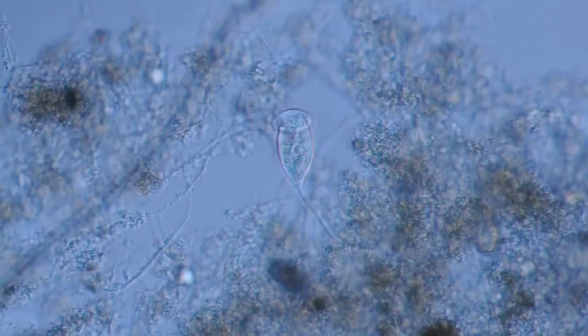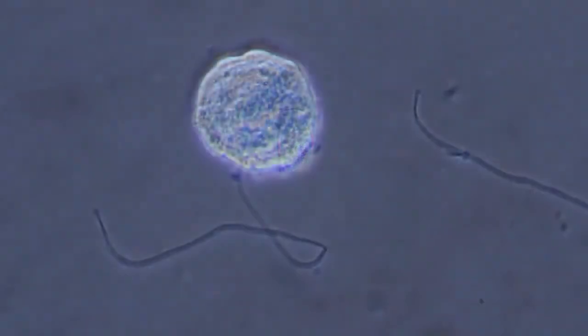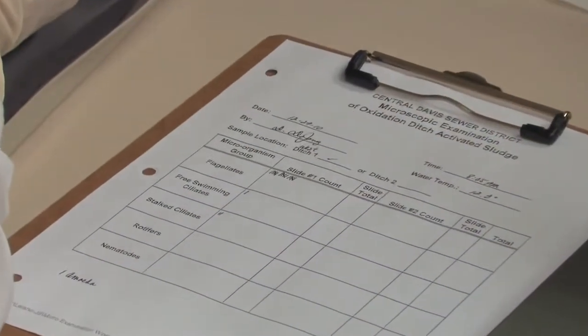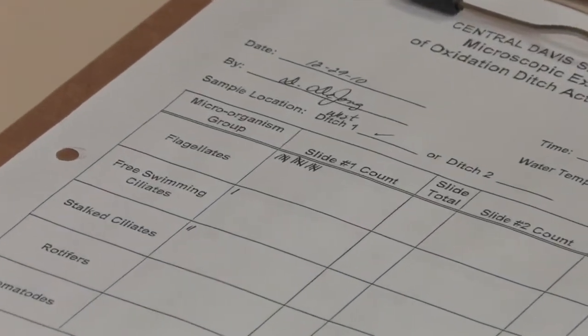Using these studies, one can see that when you see critters such as Vorticella, when you see the shelled amoebas, when you see some types of rotifers, you see those only when there's low BOD present in the wastewater. That's not always the case, but it's usually an indication that those conditions are present. The best solution for any wastewater treatment plant is to do their own analysis, prepare their own table. And if you do that, you'll be able to use the stalk ciliates, the rotifers, and the amoebas to indicate what is happening and possibly predict the future of when it's going to change.